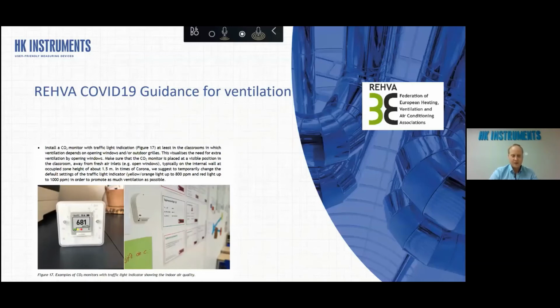So the basic rule is to make sure that the flow rates are higher than normal, and to indicate that, what you can do is measure the CO2 levels in the rooms, because that correlates to the fresh air and the flow rates. So I found out that they suggest this kind of indication for the CO2 levels, especially for schools nowadays, because in Europe, mainly in Central Europe, there are many school classes that do not have mechanical ventilation. So all they can do to make the air clean is just open the window. But then to know when it is time to open the window, they need to have some kind of indication of the air quality. And the best way to do that is by using CO2 indication.